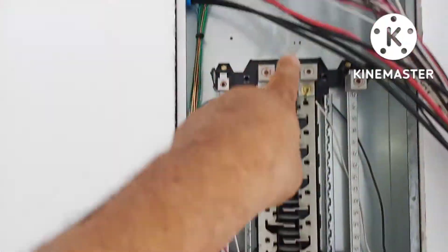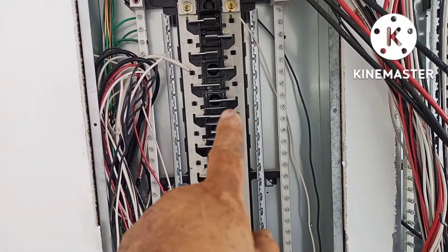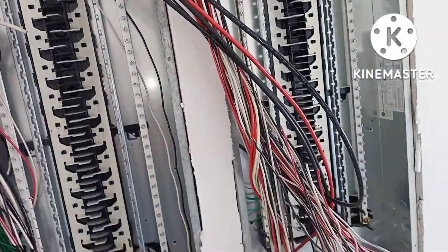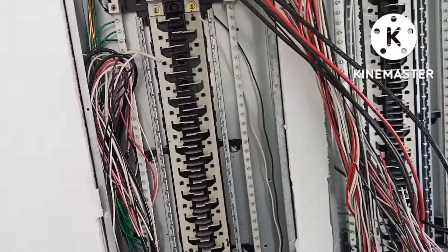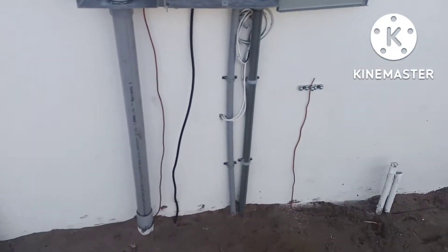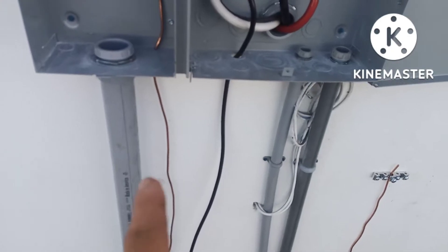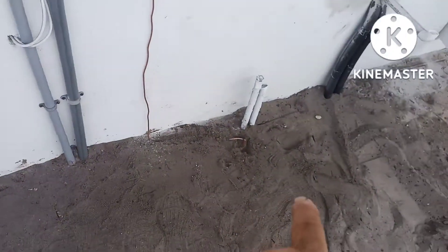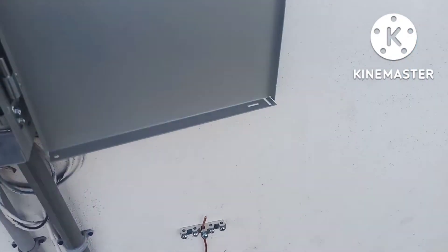Put a main breaker up there — put a 100 amp main on the bus bar here, feed it through to feed that panel until the 400 amp comes, probably next year. Okay, now I got my Ufer ground up in there. Got my number four bare copper going to both ground rods.